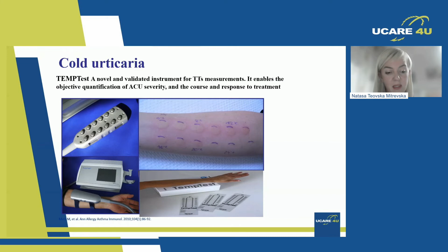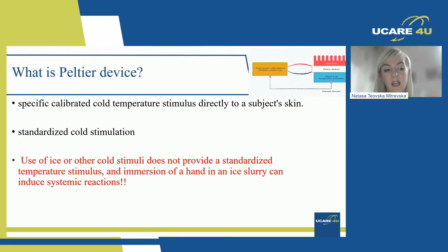So this temperature test device provides a specifically calibrated cold temperature stimulus directly to the subject's skin, and it uses a Peltier device, so it's a very standardized cold stimulation. But if we use ice or other cold stimuli, it does not provide a standardized temperature stimulus. And of course, if we do immersion of the hand in an icy slurry, we have to be aware of inducing a systemic reaction.